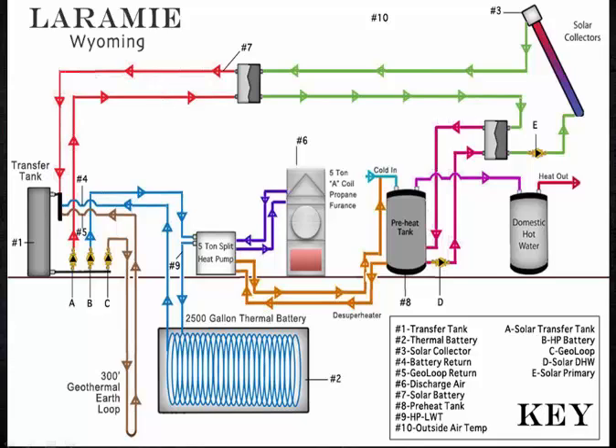We're not going to be running circulator D down there pulling heat energy off that primary loop and putting it in the domestic water preheat. We'd just be running circulator E, running the primary loop, and circulator A, which would pull off that loop and heat up the transfer tank. Then as the transfer tank reached a threshold, it would turn on circulator B and take those BTUs out and put them in the battery.